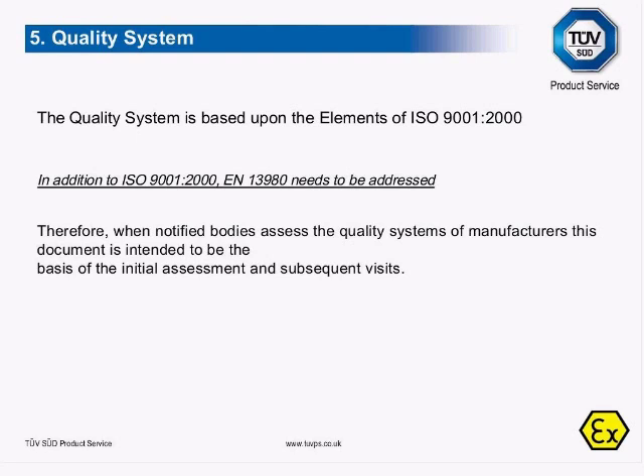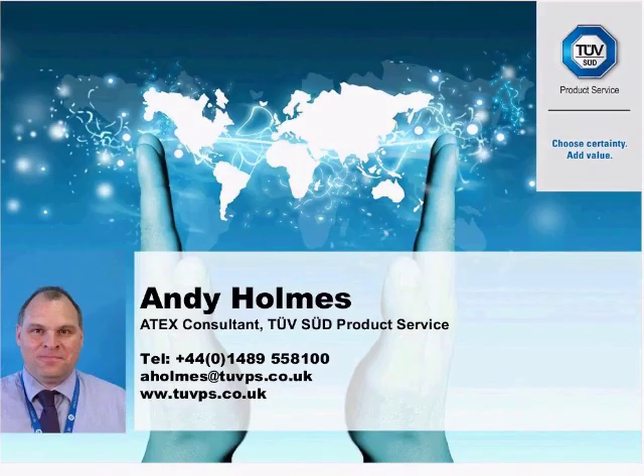Lastly, the quality system is based on the elements of ISO 9001:2000 and associated parts. In addition, ATEX also has EN 13980, which is part of the quality system. If you are looking at equipment going into Zone 0 for gases, Zone 0 and Zone 1, and Zone 20 and Zone 21 for dusts, then quality audit systems and assessments will be required. These are done on a yearly basis at the factory where the equipment is being made. And that concludes the presentation.